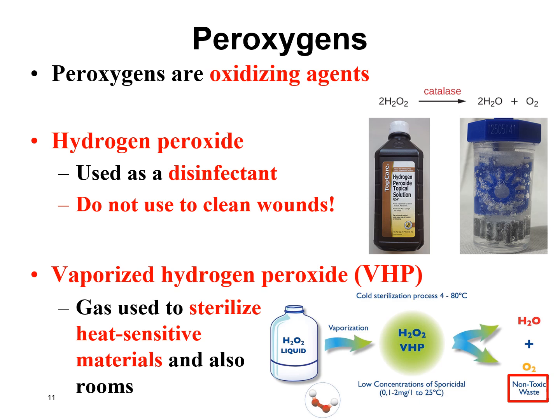And that's very good to use to sterilize heat-sensitive materials. So if you have plastics, you can run that at a low temperature and you don't have to worry about melting plastics. So some hospitals might have some sterilizers that use vaporized hydrogen peroxide.